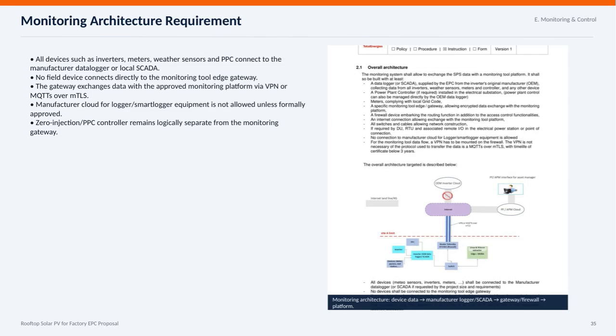Here, we are focusing on the monitoring architecture requirements for the rooftop solar PV system in the factory EPC proposal. The core idea is that device data flows from various sources, like inverters, meters, weather sensors, and the PPC, to the manufacturer's data logger or local SCADA system first. It's important to note that no field device connects directly to the monitoring tool's edge gateway, maintaining a layer of separation for security and control. The gateway then securely exchanges data with the approved monitoring platform using VPN or MQTTs over mutual TLS, ensuring encrypted communication. Also, any manufacturer cloud services for logging equipment are not allowed unless formally approved, which keeps data handling tightly controlled. Finally, the zero injection or PPC controller stays logically separate from the monitoring gateway, preserving clear boundaries within the system.